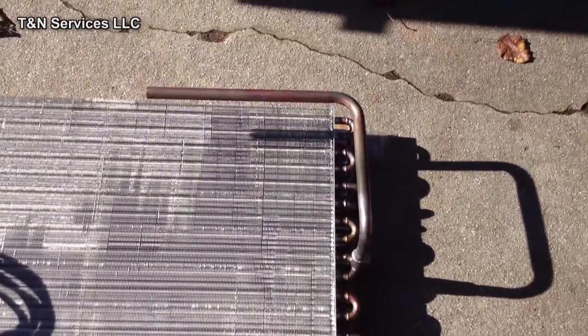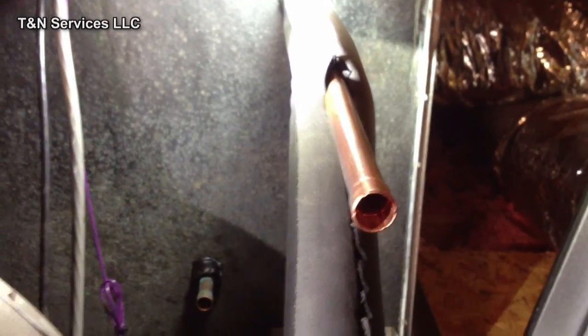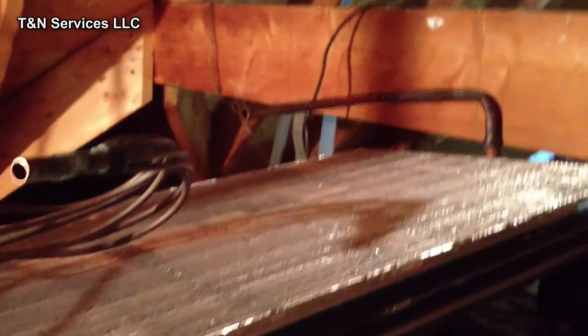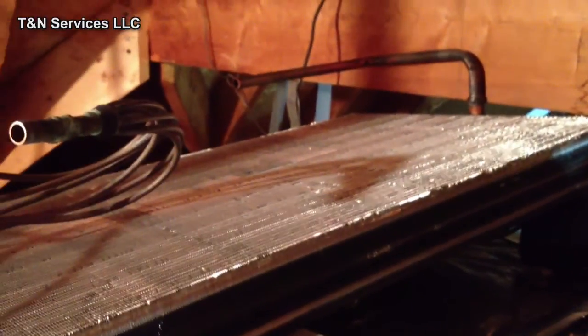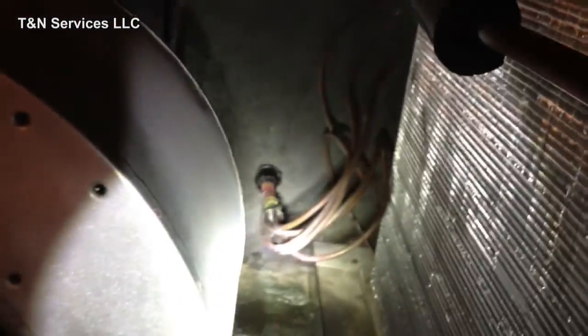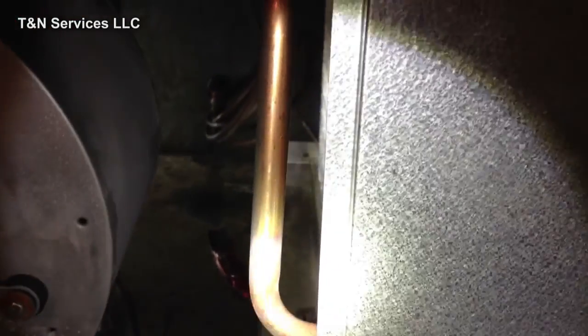We're going to take it upstairs and get it set in place and get it brazed in. I got my suction line swedged there, got my liquid line down there swedged, got my coil up here ready to be put in. I got the new coil in place, got it brazed up — brazed up down there, up there. I'm going to go get the Armaflex that I took off, get it taped up, get the vacuum pump, get the vacuum pulled on it, get the top pull put on, get the unit put back together.